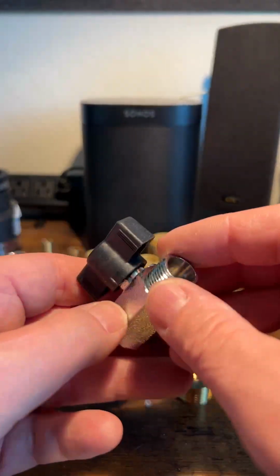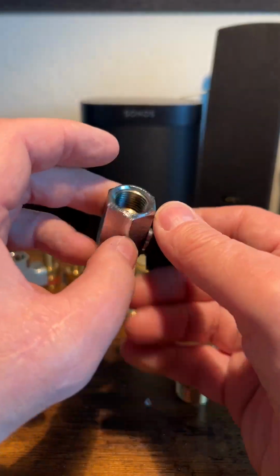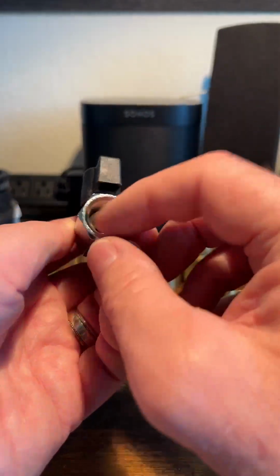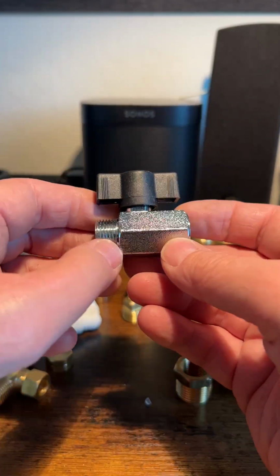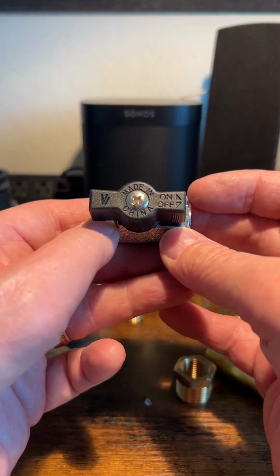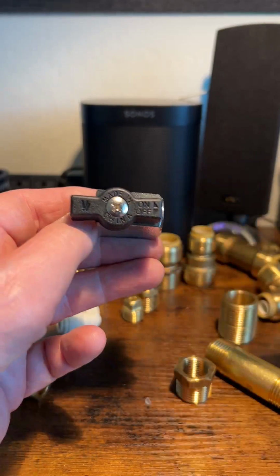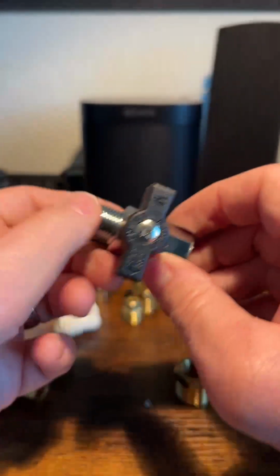If you're ordering a valve, they can come threaded or compression. You'll see compression fittings on the outside, so you can order it FIP by compression. So if I needed this valve, what would I order? I would order a 3/8 FIP by 3/8 MIP ball valve, right? And in case you didn't know, this is on, so the water would be on because this is running in the way of the pipe, right? So if I was to turn off the valve, it stops the flow.